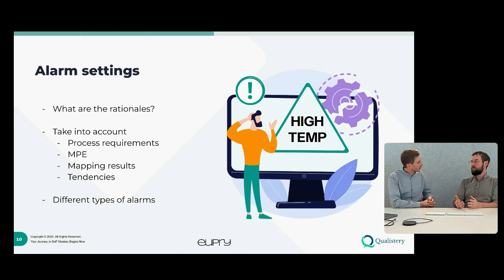A mapping report on a fridge, for example, is performed, but the results are often forgotten or not used. So when setting alarm limits, you might find a hot spot and a cold spot, meaning there are variations inside that fridge. If you place a single logger in there, do you take into account how different that spot is from the cold spot and the hot spot? That has to be deducted from the alarm settings as well.